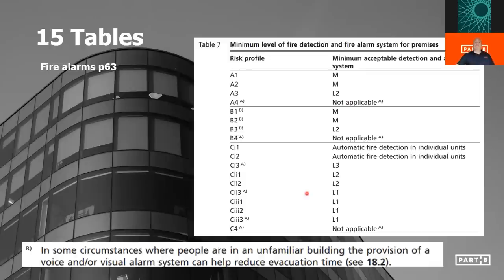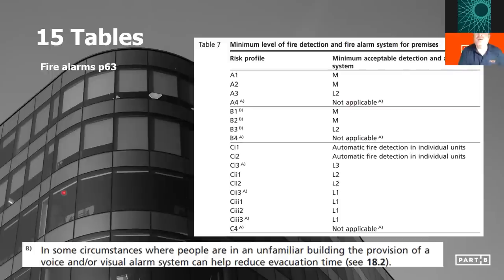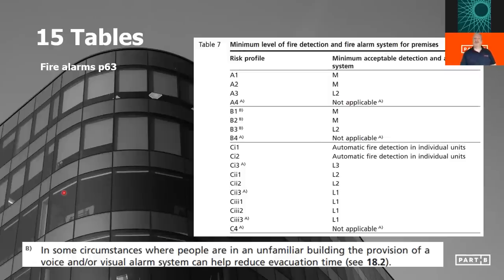Subscript B on profiles B1, B2, B3 — where we've got members of the public who can't be trained — states that in some circumstances where people are in an unfamiliar building, the provision of a voice and/or visual alarm system can help reduce evacuation time. Where you've got a voice alarm in a building predominantly occupied by employees, it may or may not have a significant effect. But it will definitely have an effect where you've got large numbers of members of the public. If you hear an alarm in a building you're not familiar with, you look around and try to get more information. But if there's a recorded voice saying 'ladies and gentlemen, please leave the building by the nearest exit, a fire has been reported,' you're going to respond so much quicker.